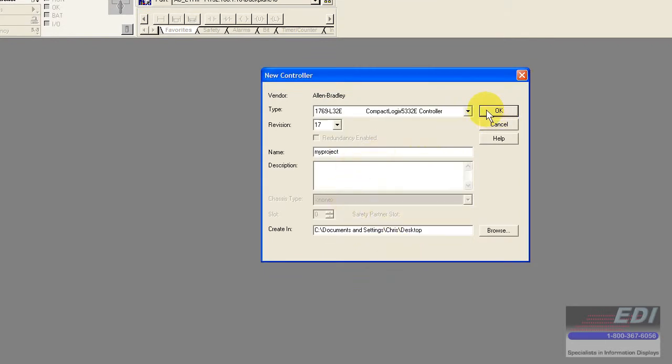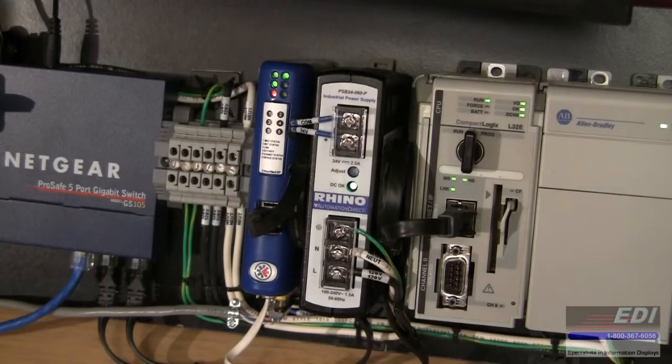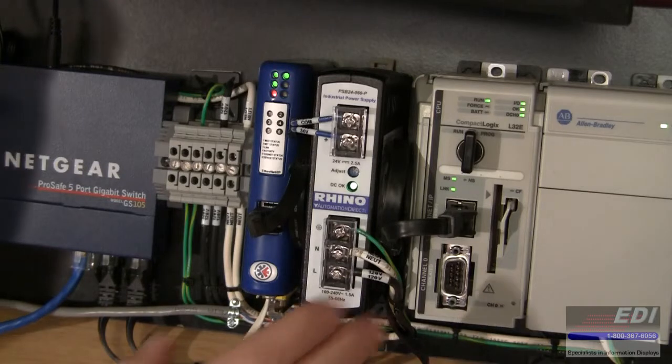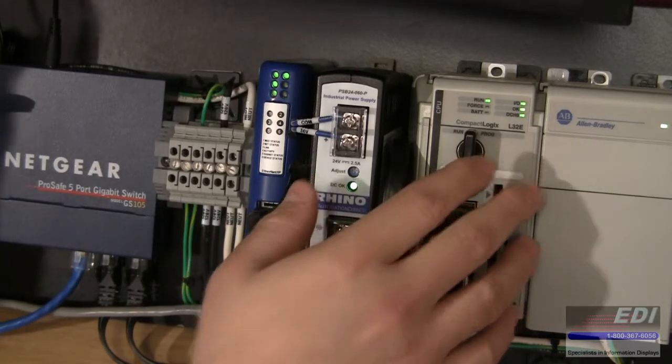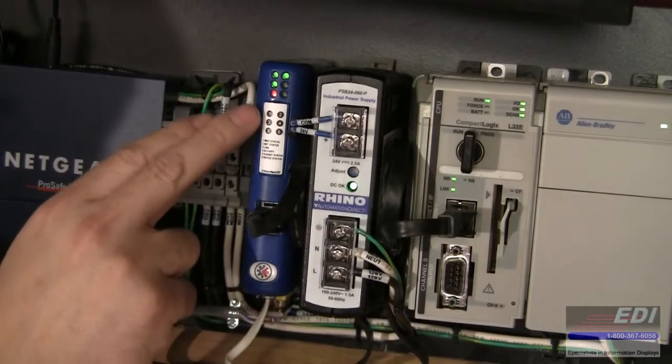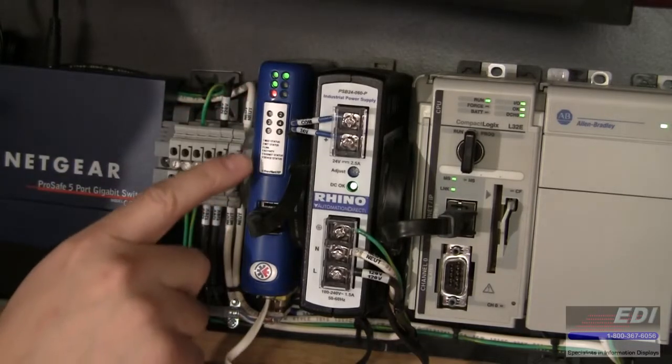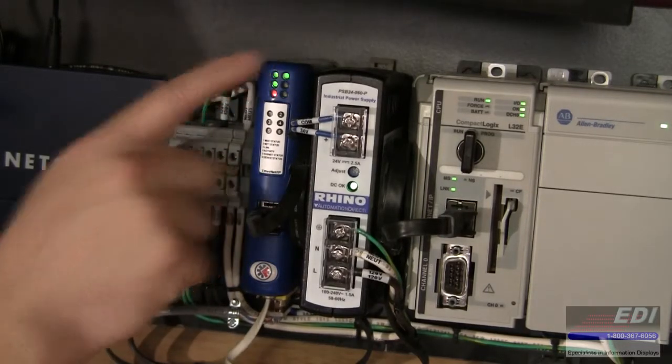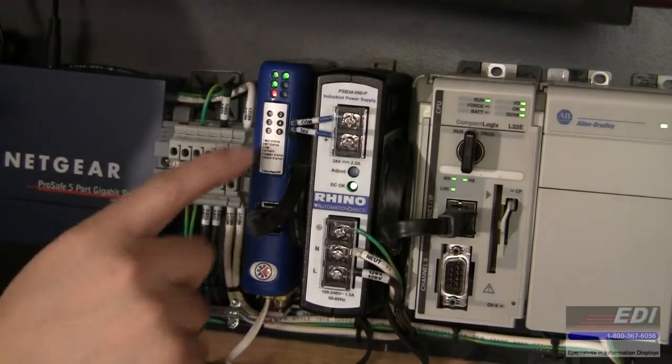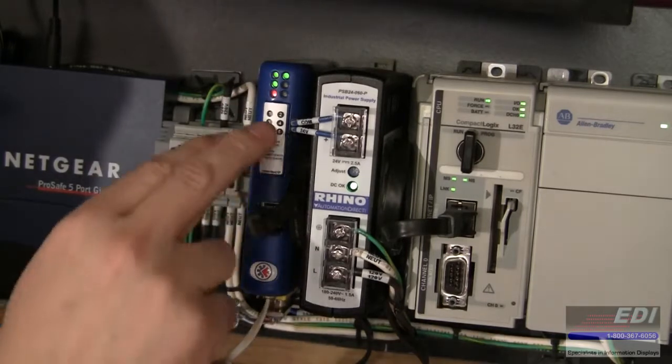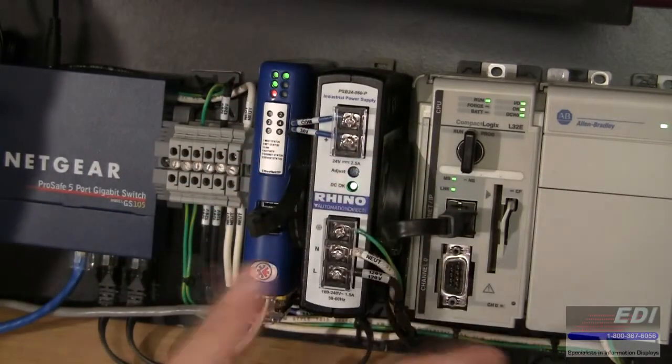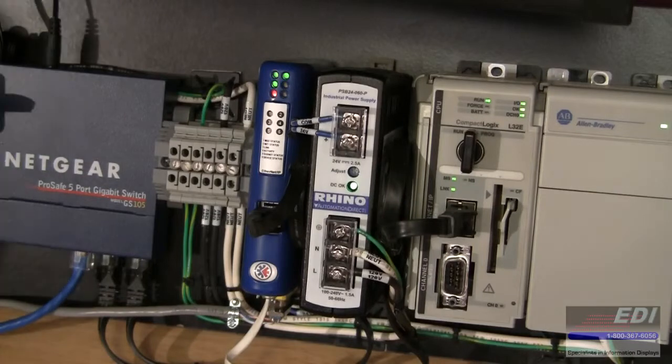Let's go back over to the camera view. You'll notice my PLC is actually on and my communicator has some status lights here. Right now I've got some blinking lights on the top which means that we are not communicating between the PLC and the AnyBus communicator yet.